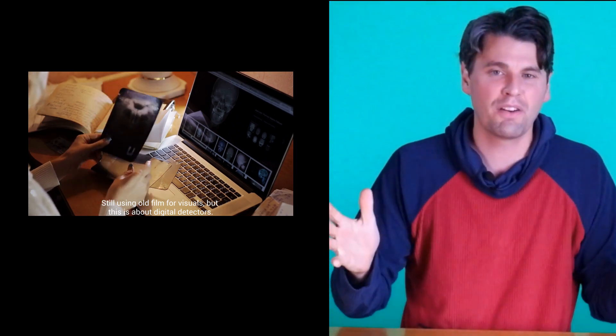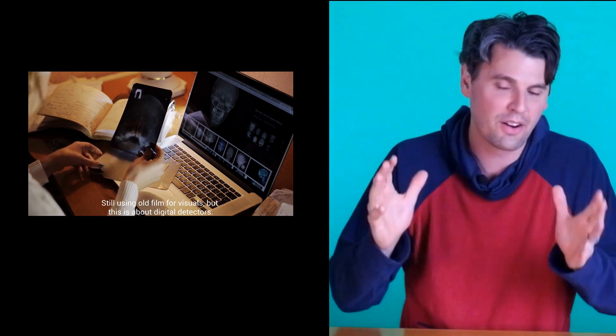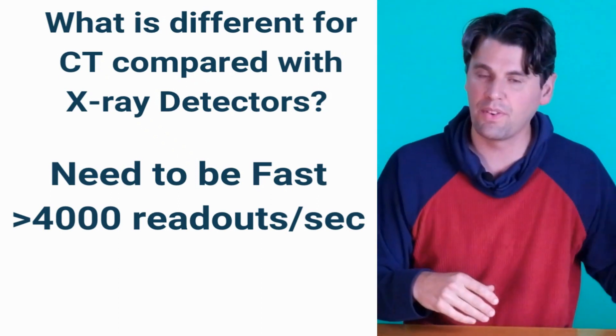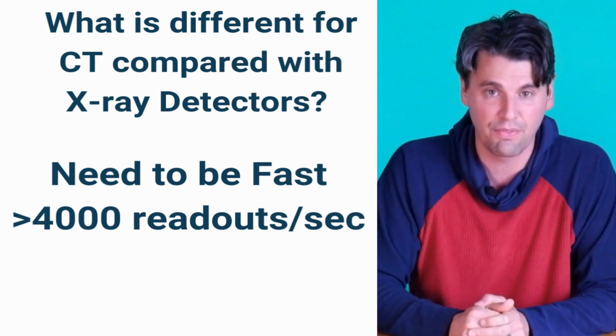In x-ray imaging you might wonder why CT is any different. CT is different for a couple of reasons compared with standard x-ray imaging. CT needs to be very fast — on a state-of-the-art CT system the fastest rotation time is 0.23 seconds. If you want about a thousand views in one rotation, that means you need more than 4,000 readouts every second. This compares with 15 to 30 readouts per second on a DR system — a couple of orders of magnitude faster.